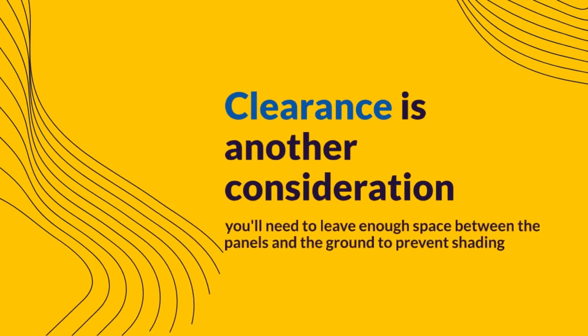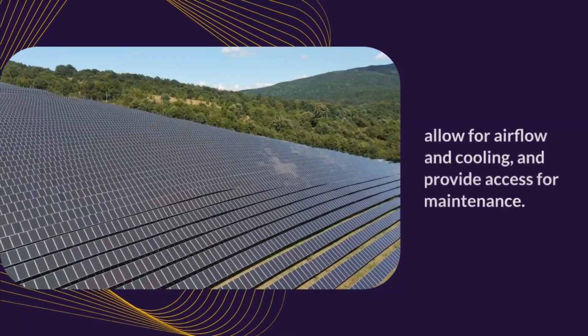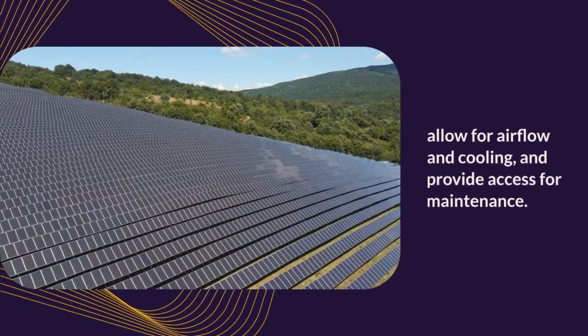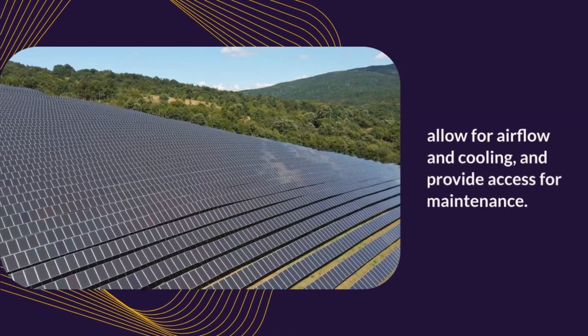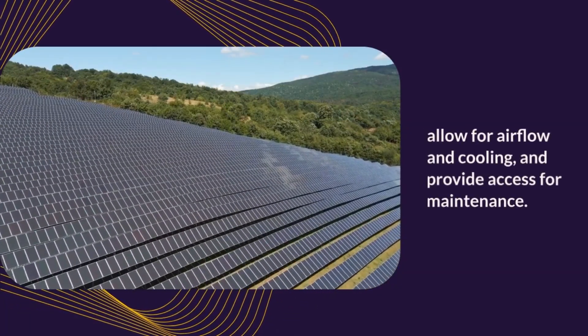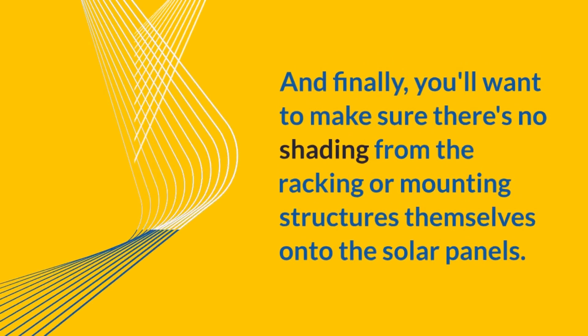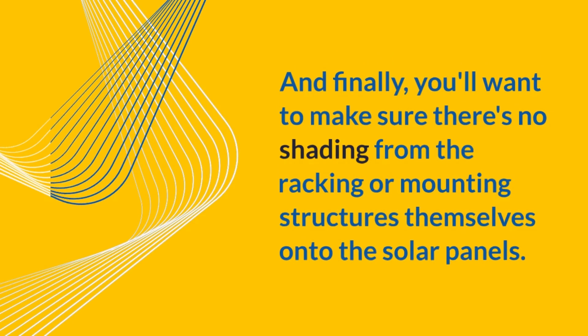Clearance is another consideration — you'll need to leave enough space between the panels and the ground to prevent shading, allow for airflow and cooling, and provide access for maintenance. And finally, you'll want to make sure there's no shading from the racking or mounting structures themselves onto the solar panels.